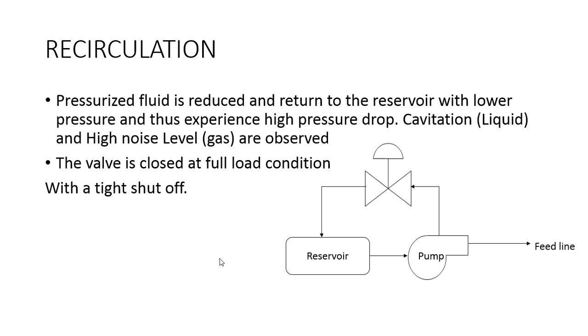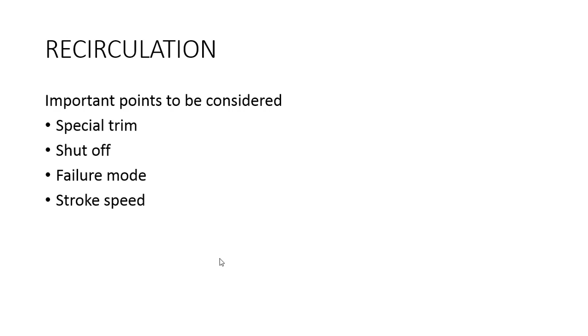The point to be considered for this one is special trim, since the valve will experience either cavitation or noise, as we discussed. A tight shut off requirement is also there, which if not followed might lose some considerable pumping power. Failure mode will be fail open, and the stroke speed will be within 2 to 5 seconds for compressible fluid and up to 25 seconds for incompressible fluid.